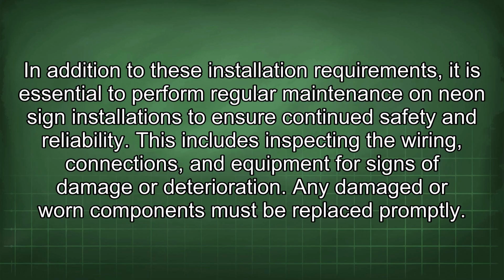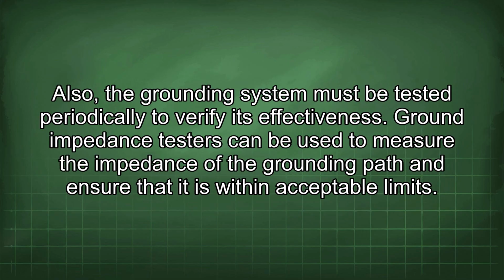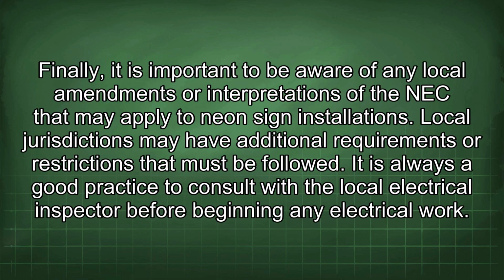Any damaged or worn components must be replaced promptly. Also, the grounding system must be tested periodically to verify its effectiveness. Ground impedance testers can be used to measure the impedance of the grounding path and ensure that it is within acceptable limits. Finally, it is important to be aware of any local amendments or interpretations of the NEC that may apply to neon sign installations.